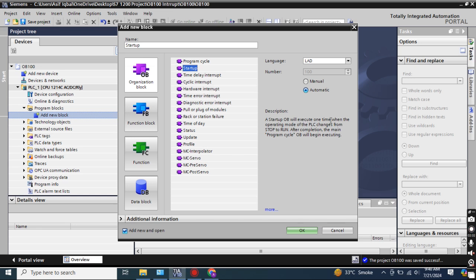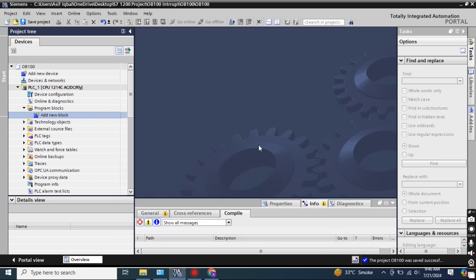The startup OB will execute one time when the operating mode of the PLC changes from Stop to Run. After completion, the main program cycle OB will begin executing. This is the main advantage and purpose of OB-100. Just click OK.